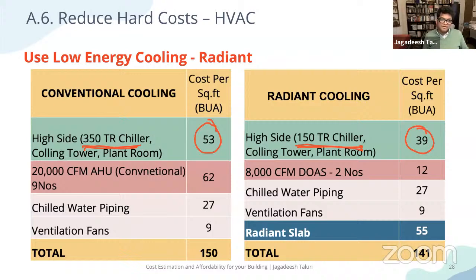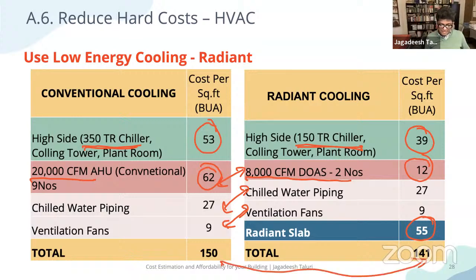Another thing is that from conventional to radiant buildings, the number of AHUs and the ducting is much less. Instead of 20,000 CFM AHUs, 9 numbers, you can do the same thing with 8,000 CFM DOAS, 2 numbers. So instead of spending 62 rupees a square foot, you can do the same thing in a better way for 12 rupees a square foot. Your chilled water piping may be the same, and your ventilation fans may be the same. Even if you have added 55 rupees more for the radiant slab and all the other systems, your total cost, as you have seen, is less than a conventional system.